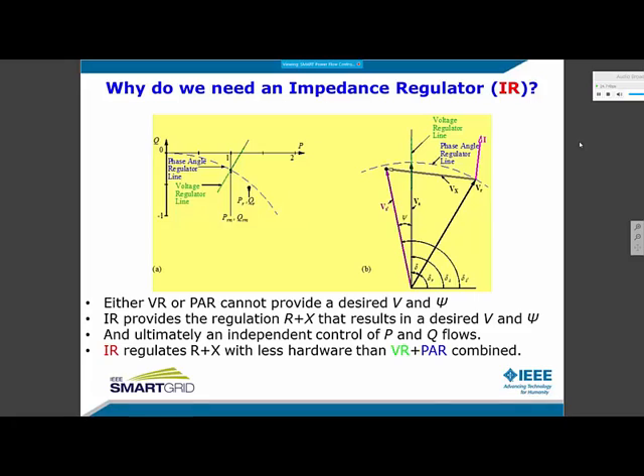The voltage and power flow profile of the voltage regulator and phase angle regulator are well established for more than a century. So why do we need a phase angle regulator, or why do we need an impedance regulator? For a desired PQ flow, for example, this point in this figure, the line voltage must be changed from an original voltage to a new voltage with a new magnitude and phase angle that may not be fulfilled either by using a voltage regulator or a phase angle regulator.